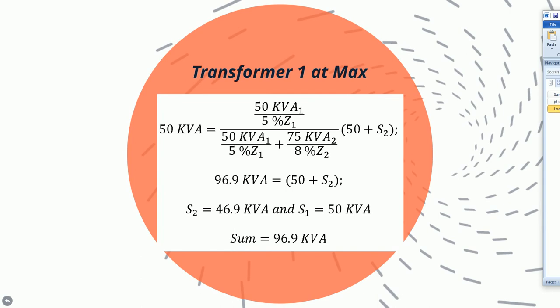First, let's assume that Transformer 1 is maxed out at its rated capacity of 50 kVA. We plug in the values of the rated capacity and percent impedance for Transformer 1 and Transformer 2 in order to solve for S2, the power flow through Transformer 2. After solving, we find that S2 is 46.9 kVA, and the assumed power flow through Transformer 1 is 50 kVA, giving a sum of 96.9 kVA.